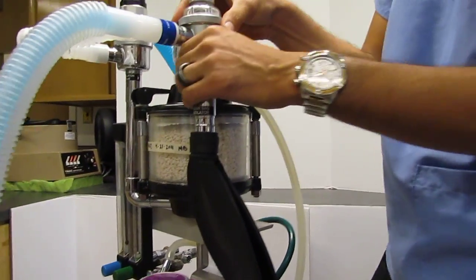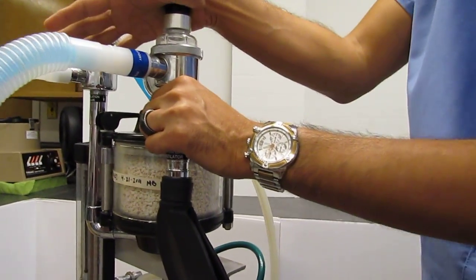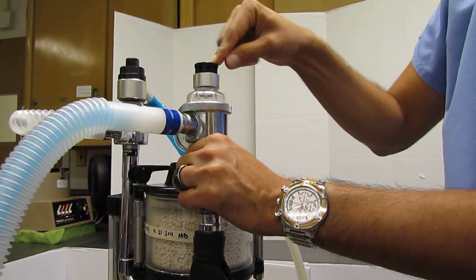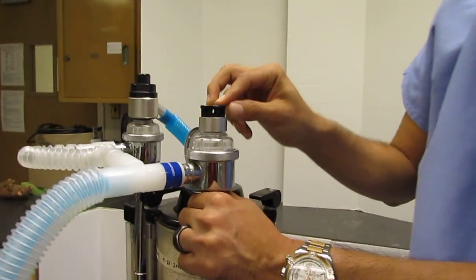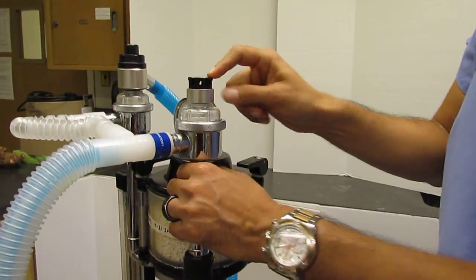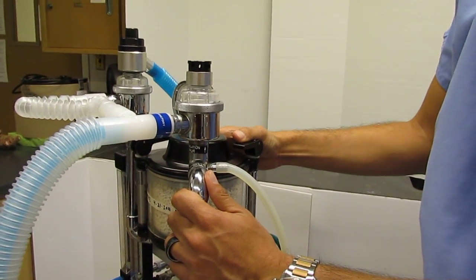So, my one-way, unidirectional inspiratory valve, that one also has a valve above it, which is called the negative pressure safety valve.